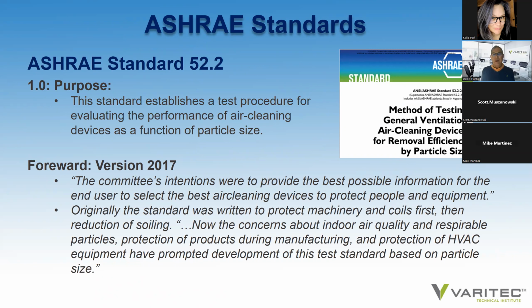However, the pandemic introduced the realization that you can remove more contaminants and pathogens from the space by using more efficient filtration. They recommend a minimum of MERV 13, ideally MERV 14. If you hear these terms, they're all in reference to Standard 52.2, which defines the testing methodology of filter media and their effectiveness and efficiency in removing contaminants and particulates from the air.